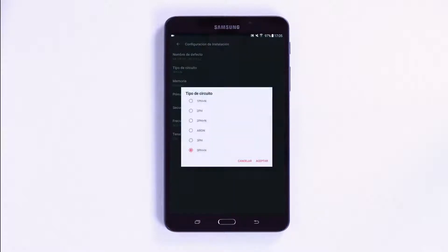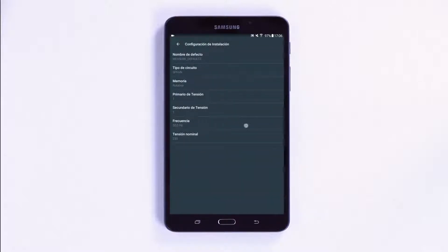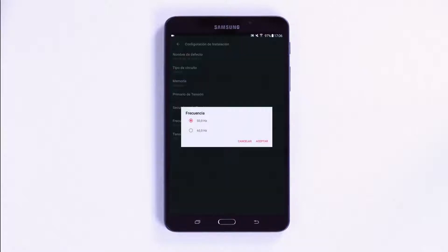By accessing the installation menu and pressing installation setup, you can configure parameters such as the name of the installation or the type of circuit being measured. It is also possible to change the memory format — rotating or linear — or values such as the primary and secondary voltage.